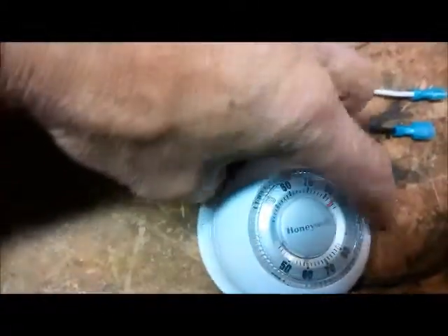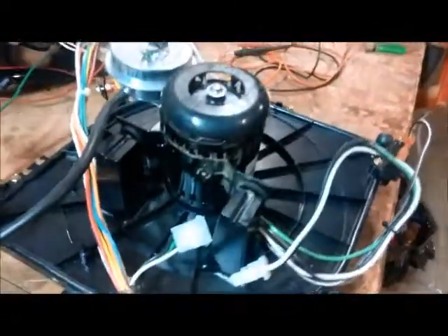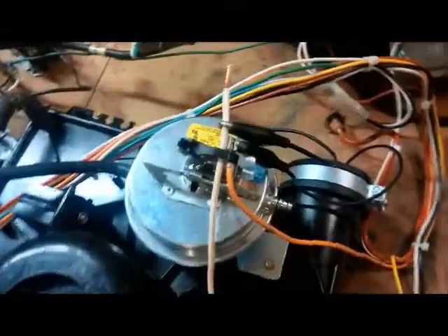So say we initiate a call for heat at the thermostat, turn it to heat, turn it up, the inducer motor should be running, and the pressure switch, these two wires right here, the white wire and the orange wire, would be connected to the pressure switch. And right now it's not, and this should go into a fault here shortly, because the inducer motor should be running right now. And we should get a 3 flash code here shortly.